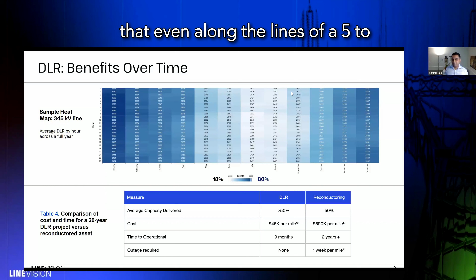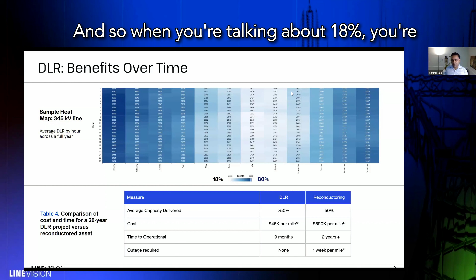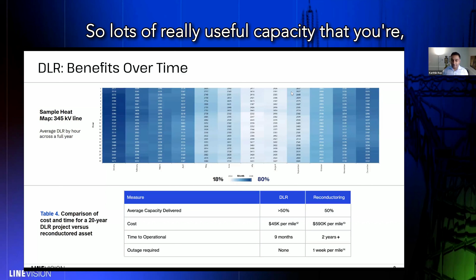That's still really significant when you take into account that studies have shown that even a 5 to 10% increase in capacity is typically enough to essentially eliminate congestion on any given line. And so when you're talking about 18%, you're already likely eliminating congestion on that line altogether. And from there, it's just additional headroom depending on which season of the year you're in. So lots of really useful capacity that you're able to get year round. Yeah, agreed.